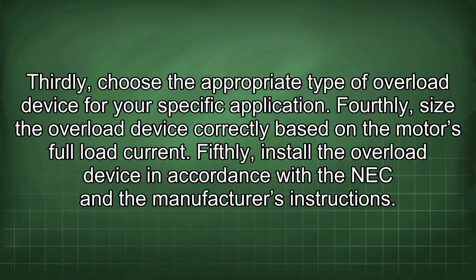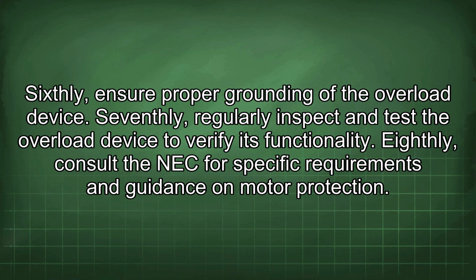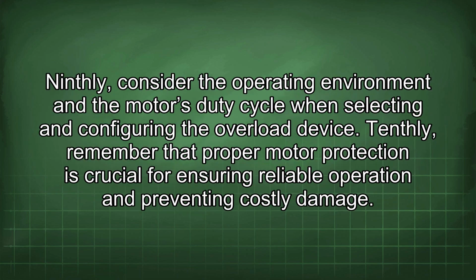Fifthly, install the overload device in accordance with the NEC and the manufacturer's instructions. Sixthly, ensure proper grounding of the overload device. Seventhly, regularly inspect and test the overload device to verify its functionality. Eighthly, consult the NEC for specific requirements and guidance on motor protection. Ninthly, consider the operating environment and the motor's duty cycle when selecting and configuring the overload device. Tenthly, remember that proper motor protection is crucial for ensuring reliable operation and preventing costly damage.